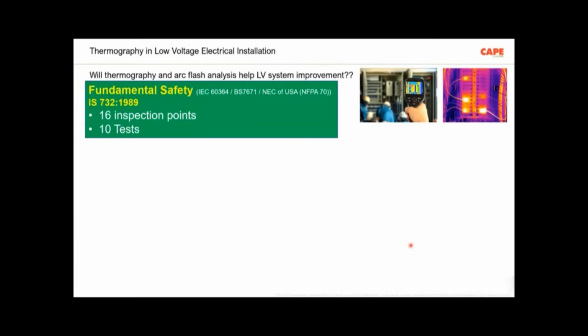Let us analyze whether thermography and arc flash analysis help low voltage system improvement. We are talking about low voltage, not the other voltages. Please understand, in low voltage engineering, there are fundamental safety requirements, that means the basic safety requirements. They are included in IEC 60364, that is the IEC standard. In the British standard the same is BS 7671, or NEC of America, NFPA 70, or IS 732, the code of practice of wiring, for us.